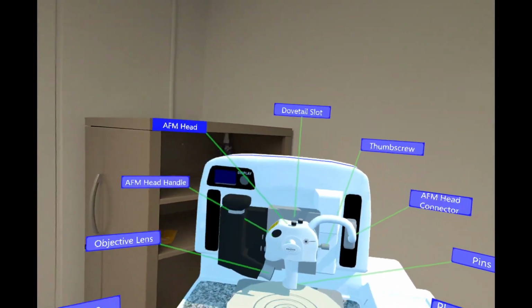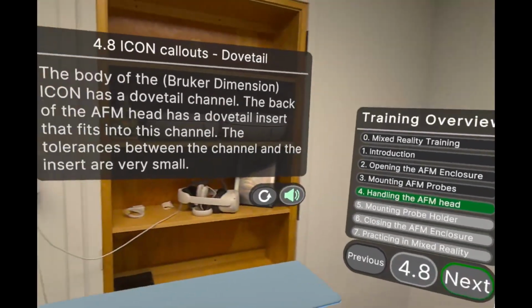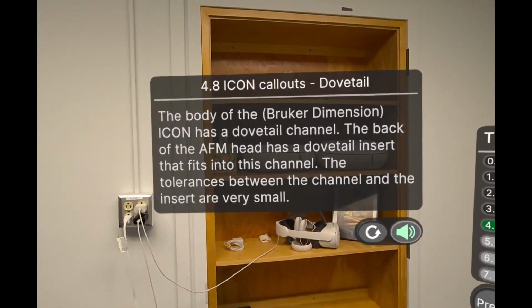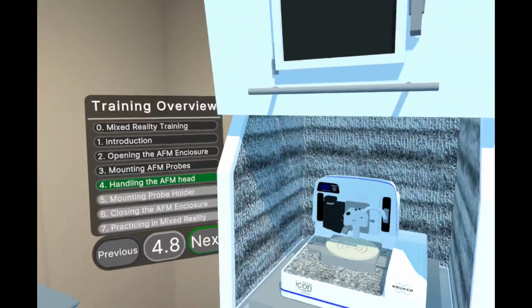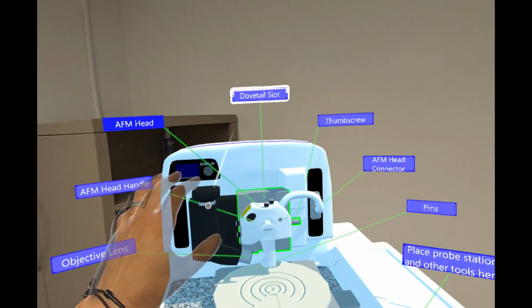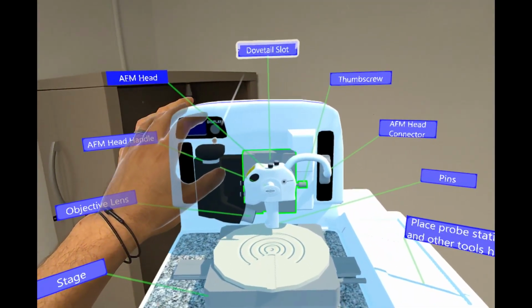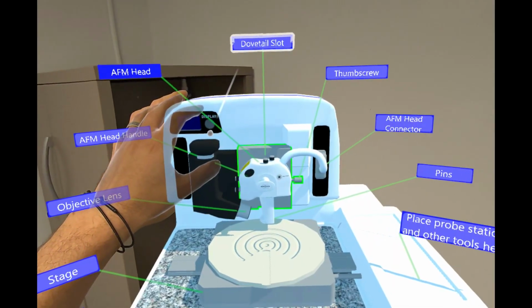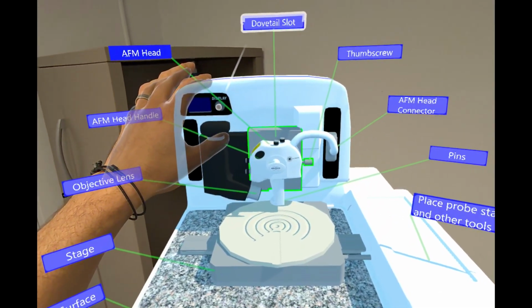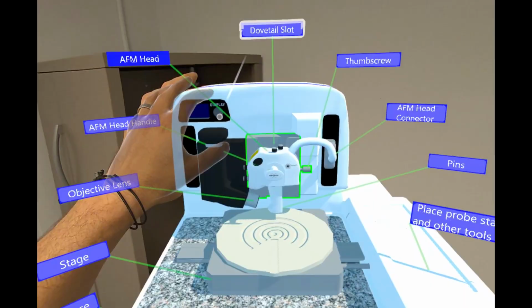The body of the Bruker Dimension Icon has a dovetail. The back of the AFM head has a dovetail insert that fits into this channel. The tolerances between the channel and the insert are very small. This makes lifting the AFM head out of the channel difficult unless done near perfectly.